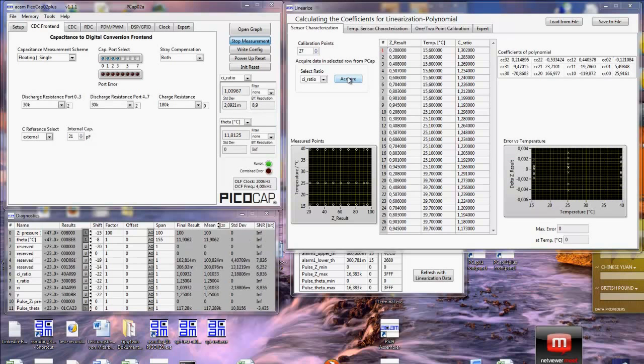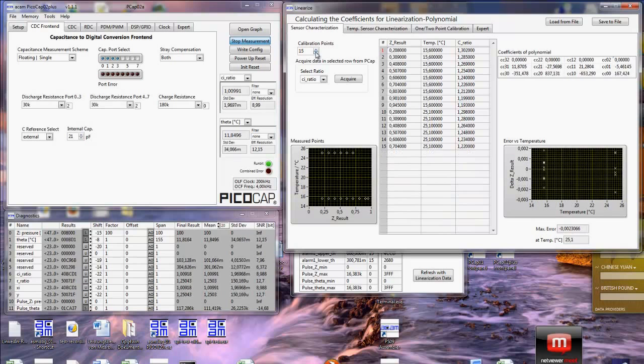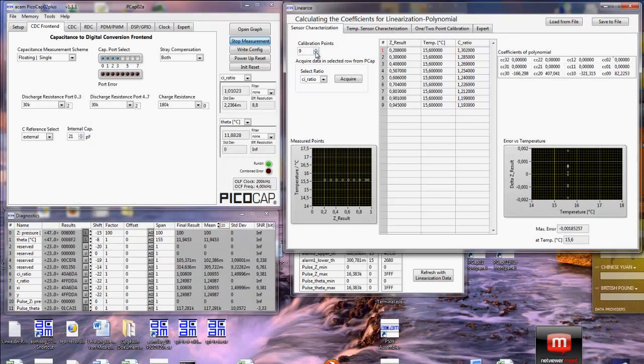In this first tab page, you can very flexibly select the number of calibration points you want to set. So let's say we want to do a sensor calibration at 2 temperatures and over a range of pressure points. So for example 0% pressure, 10%, 20% pressure, and so on. So in this case, right here in the pressure point I'm planning to set, for example, 0% pressure, 10% pressure, you give this in as a 0.1 value here, then 0.2 would reflect 20% pressure, 0.3 30, and so on. So I just do that for the whole row until we get 100%.